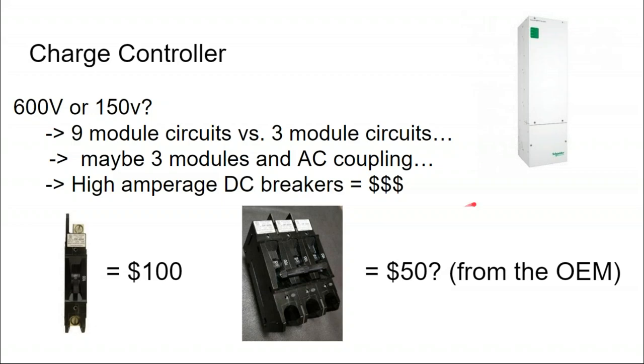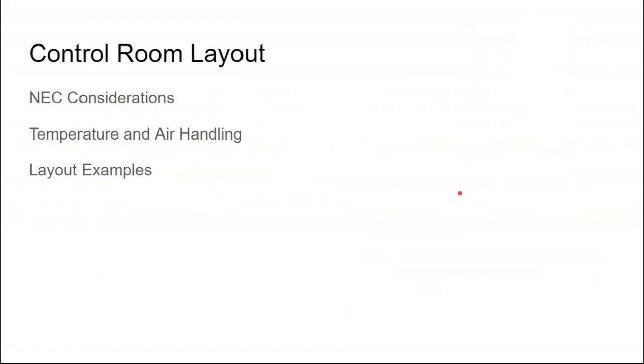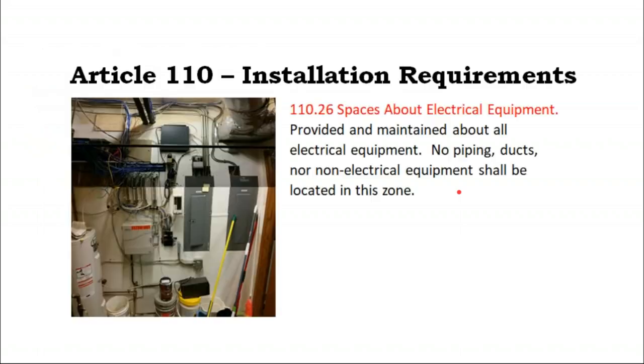It becomes quite expensive. So I don't know, I mainly do DC coupled solar arrays, but I buy the arguments of the AC side, AC coupling as well. The fact is, if you're putting the solar array on the rooftop, National Electric Code all but mandates that you're going to have an AC coupled solar array, because whether you're using Enphase microinverters or DC solar optimizers to meet the rapid shutdown requirements, you're either using the Enphase system or the SolarEdge system. And the Enphase, by its nature, inverter on the rooftop means you're going to AC couple. So SolarEdge, they do both—they have a kind of DC coupled battery that can also be an AC coupled battery.